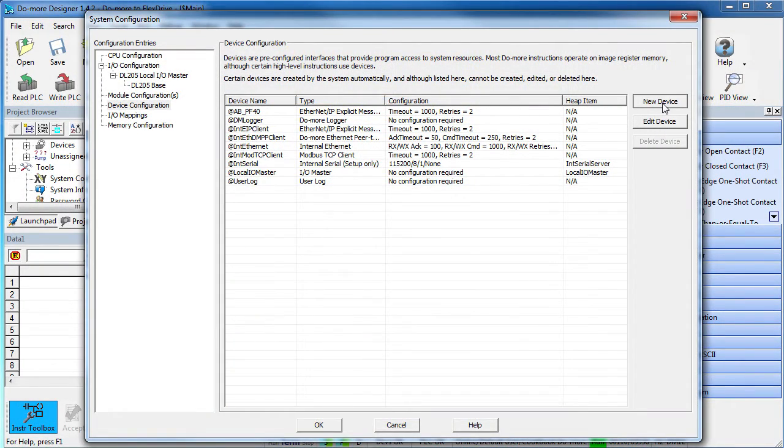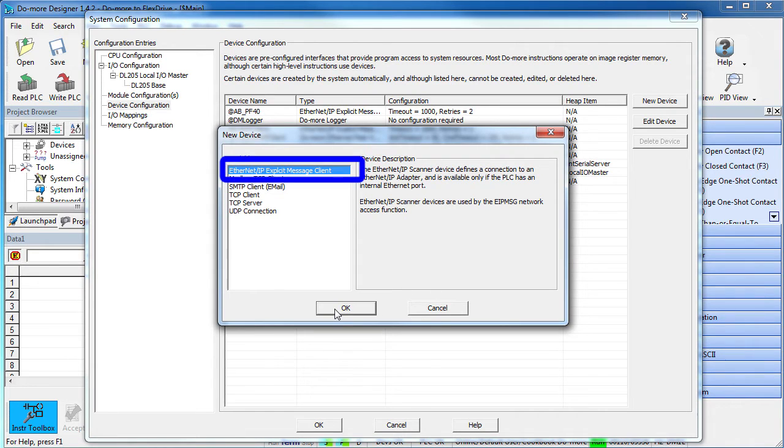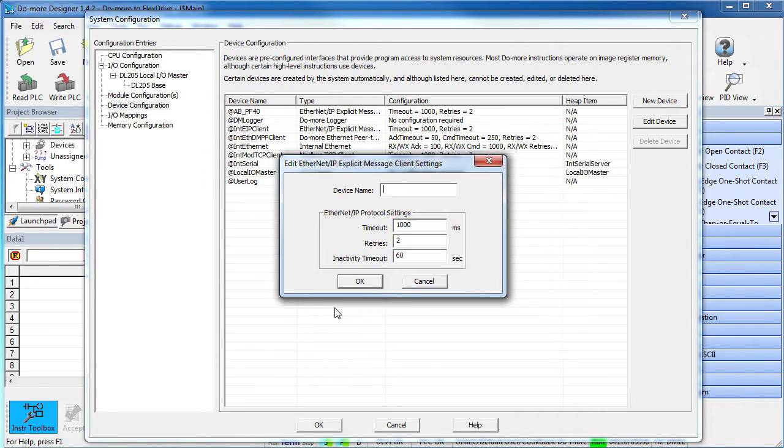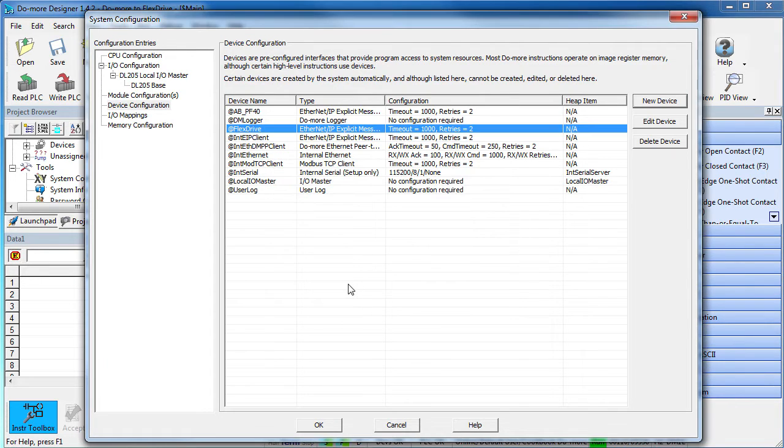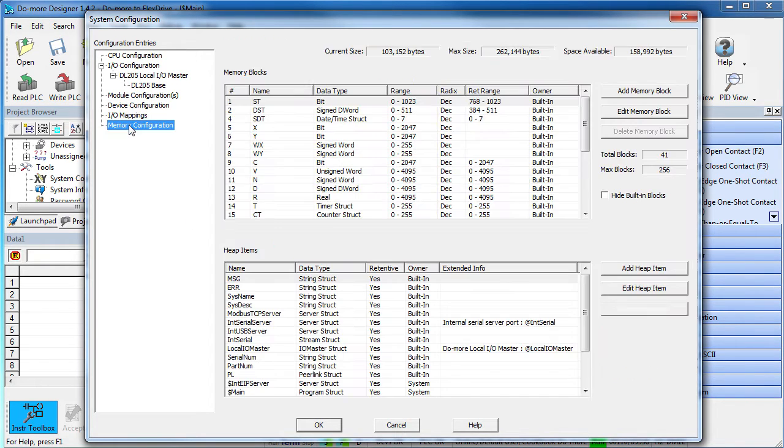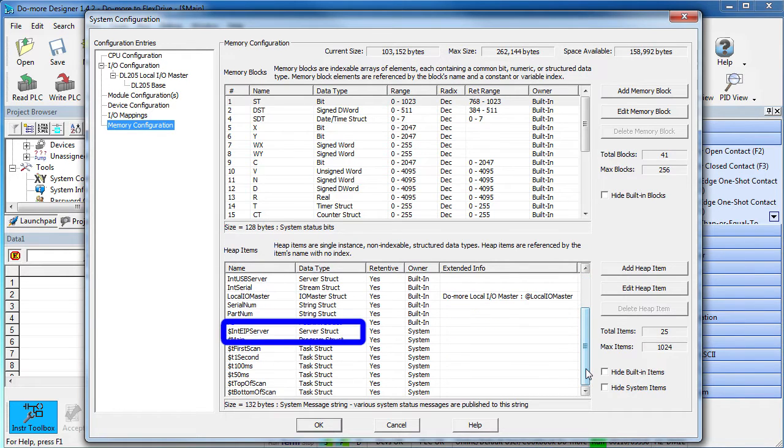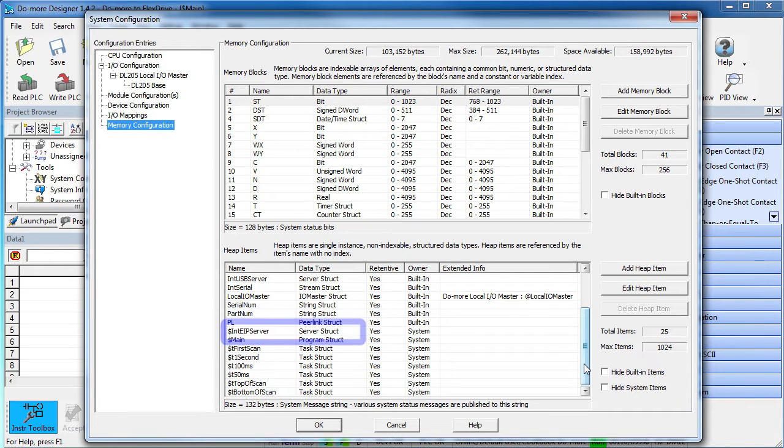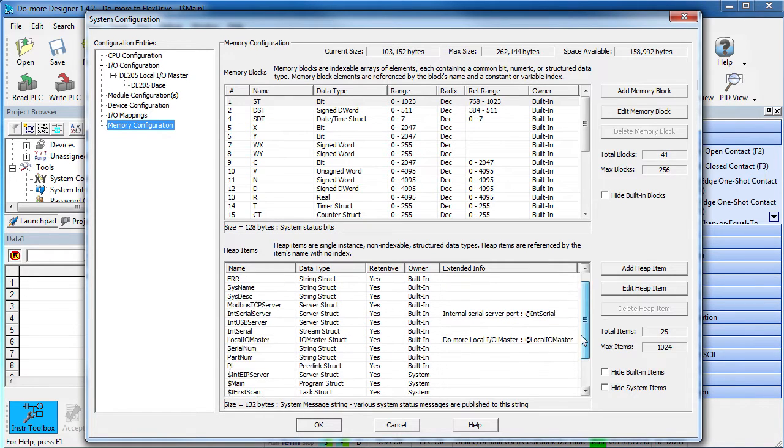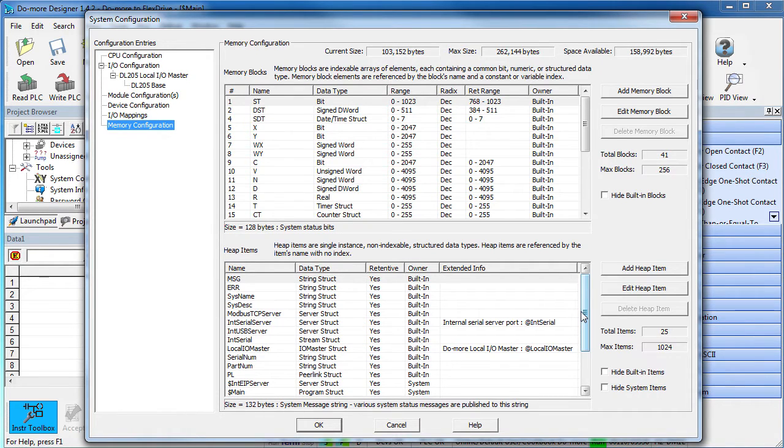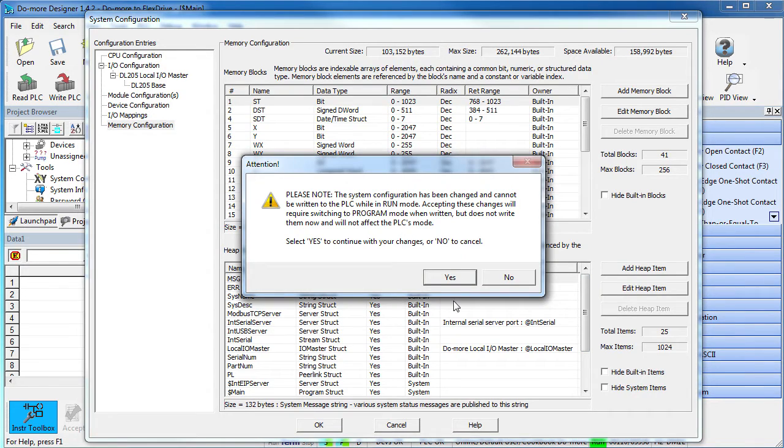So we'll create a new Ethernet IP device specifically for this flex drive. New device, Ethernet IP client, OK. We'll give it a name, how about flex drive? And the rest of this looks fine. That's it. We just created a device we can talk to. There is no associated I.O. mapping and no new structure because there is nothing for us to interact with with this Ethernet IP client. Notice that there is a structure for the Ethernet IP server. Some people call that a slave. We'll see that in action in the video where we use the DoMore as a server to another device. For this video, the DoMore is a client or a master device.